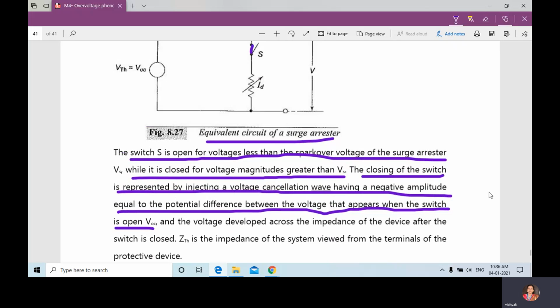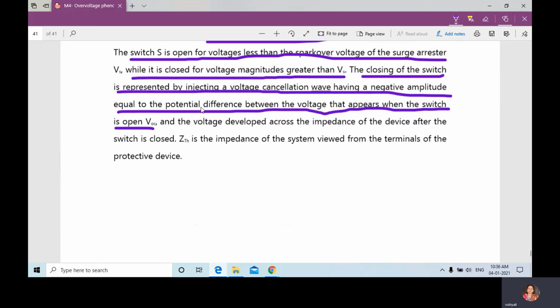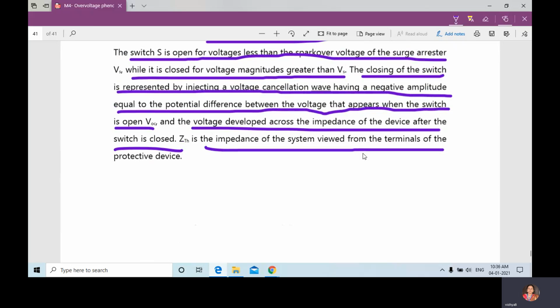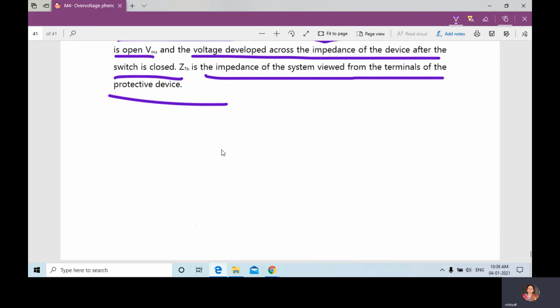The injected voltage cancellation wave has a negative amplitude equal to the potential difference between the voltage that appears when the switch is open circuit. It is almost equal to the VOC. The voltage will be the same when the switch is closed also. And the voltage developed across the impedance of the device after the switch is closed, ZTH, is the impedance of the system viewed from the terminals of the protective devices.